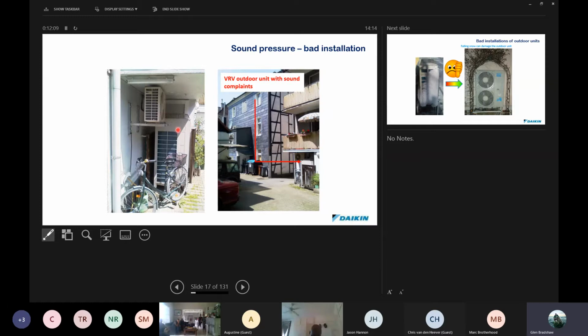What's happening? Well, first of all we've got a very good setup here for recirculation of condenser air, which means that the condenser may have to increase the fan speed to try and reach the target condensing or evaporating conditions, depending on whether it's in heating or cooling. And with that increase in fan speed, we generate more noise. And because this condenser over here would also be responding to what's happening from the condenser at the back, once we create a situation like this, we create a knock-on effect, and the sound can continue and become worse as the unit tries to deal with its poor installation.